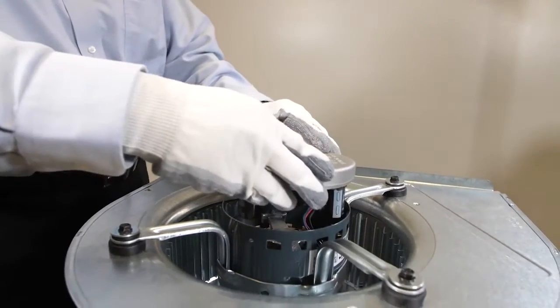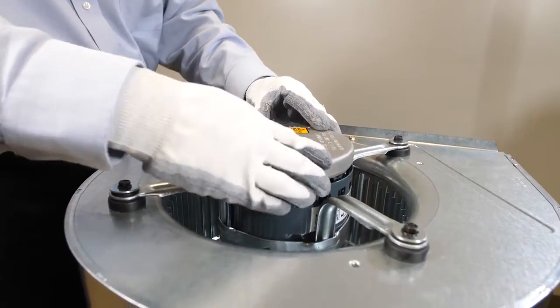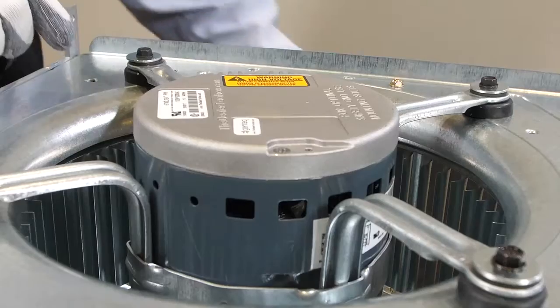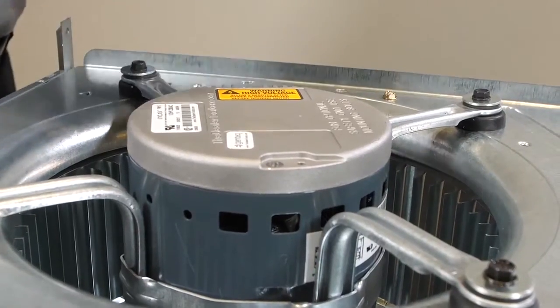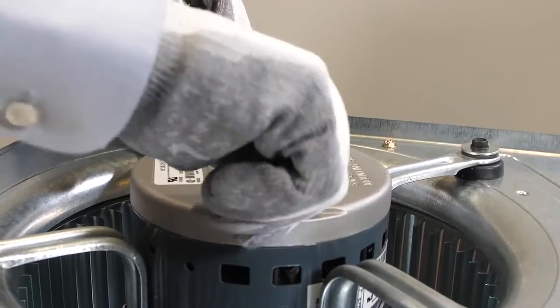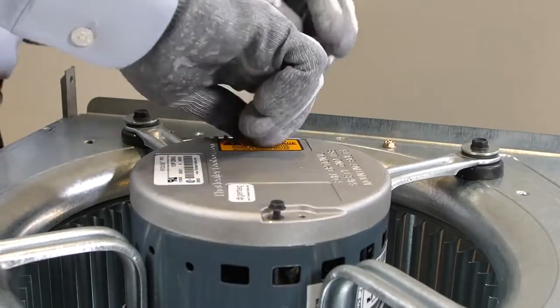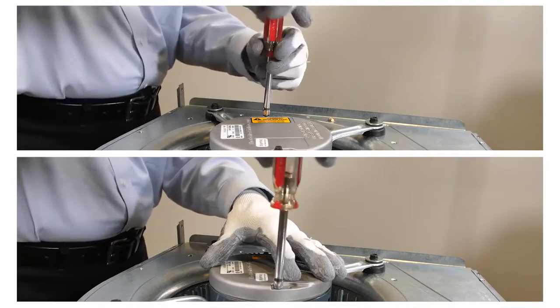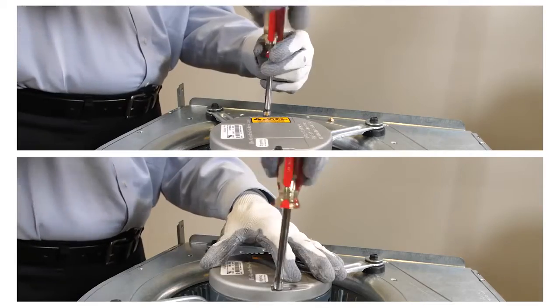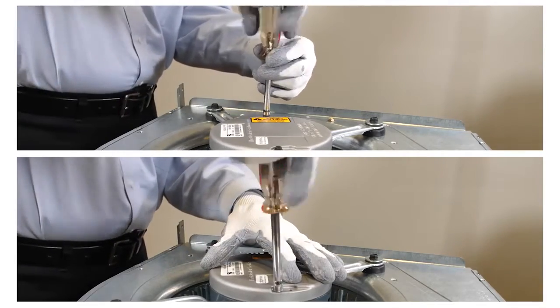Make sure the connector is fully seated and latched and align the power connector and aluminum heat sink with the notches on the motor housing. Insert the previous hex bolts or utilize the new ones provided in the replacement kit. Start the bolts by turning a few threads on each one and then fully tighten once they are all in place. Be careful not to over tighten the bolts. Over tightening the bolts may result in bearing noise and reduced life of the module.